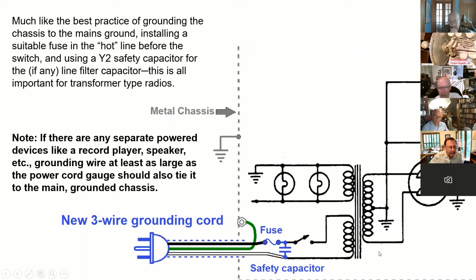So Rob, do you have a typo there? Because shouldn't that be an X2 capacitor? No, it could be an X2 capacitor, but again, the X2 is designed to fail shorted, and that's supposed to cause a short circuit and let you know that I no longer have my line filter on it. Whether it's going to line to ground or across the two lines, it's probably better to use a Y2 safety capacitor, in my opinion.